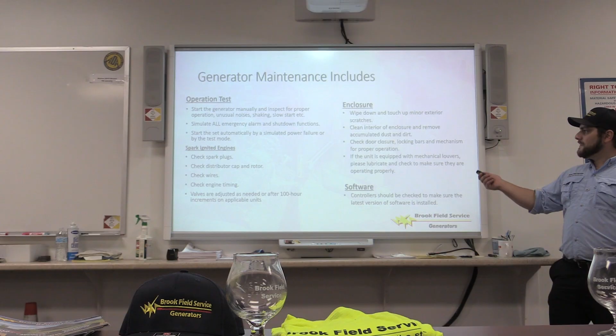Don't forget the transfer switch. We're certified to do things you're really not supposed to be doing yourselves, especially cleaning and adjusting relay fingers, checking the condition of main arcing contacts and auxiliary contacts, and lug connections - things that require PPE and a licensed electrician or technician to check. And of course, giving the TLC to the enclosure as well.